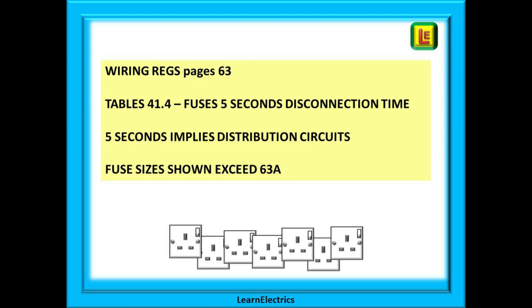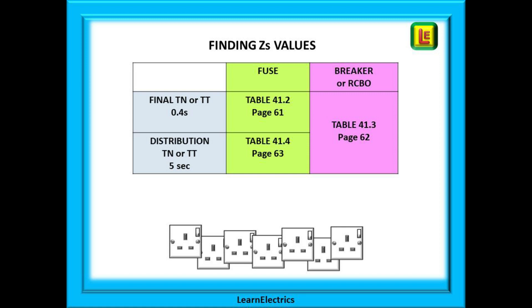On page 61 we find the table for fuses specifically for 0.4 second disconnection times, implying final circuits — notice that fuse sizes shown do not go past 63 amps on this table. On page 63 we find table 41.4 for fuses again, but specifically for distribution circuits with five second disconnection times, and on this table the fuse sizes do go past 63 amps.